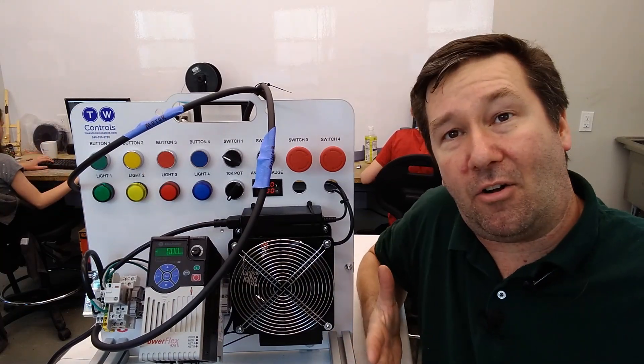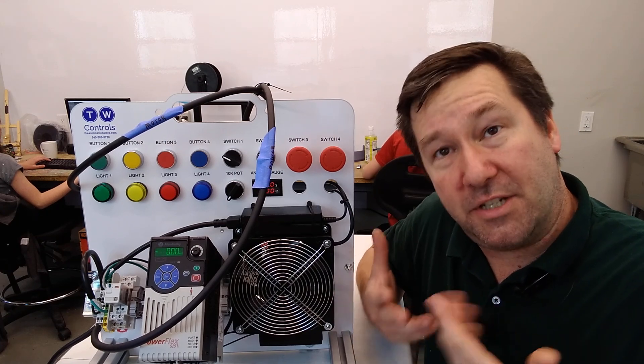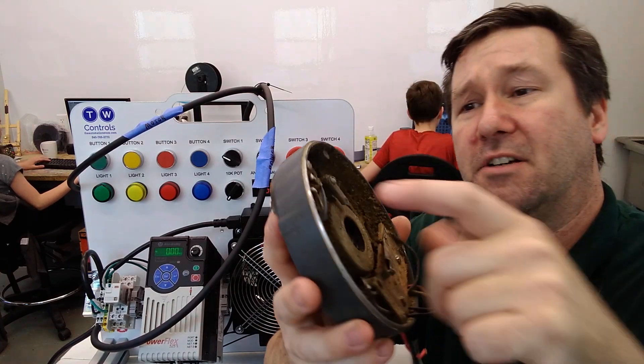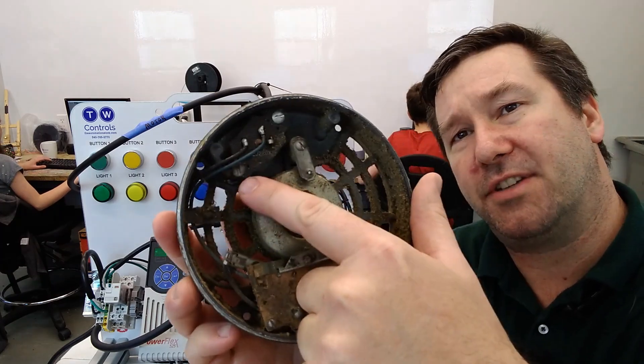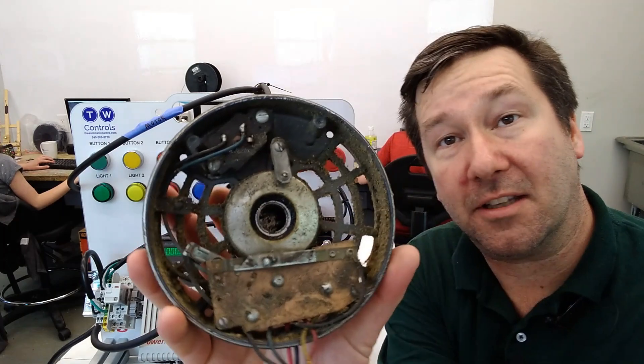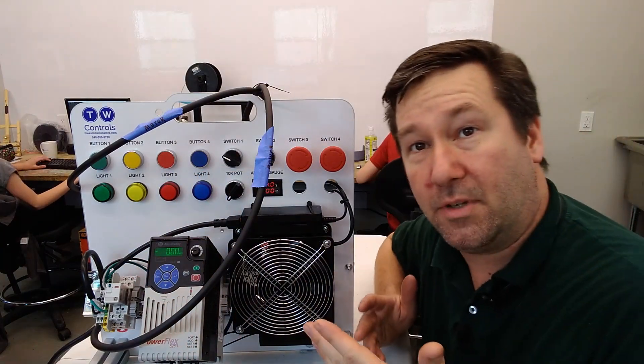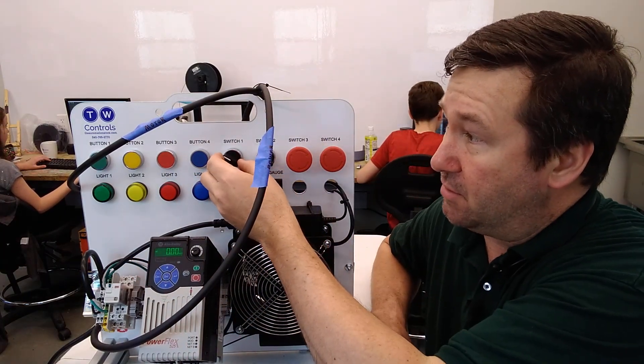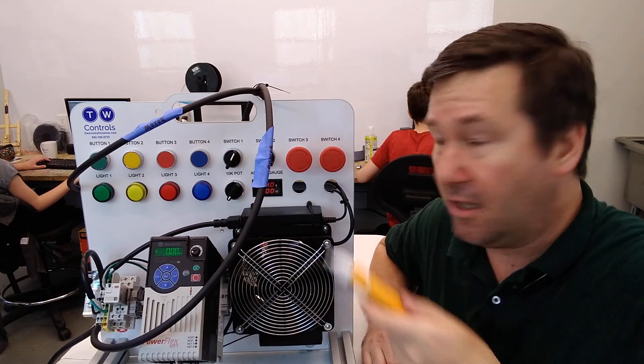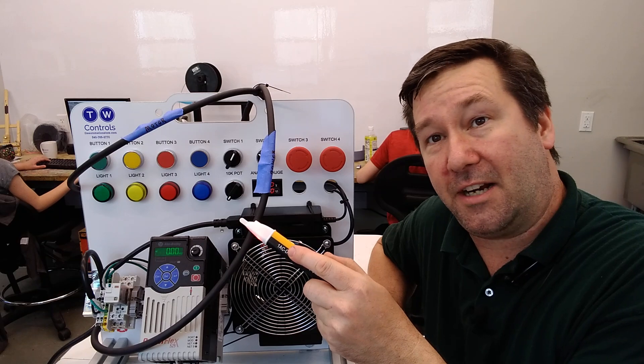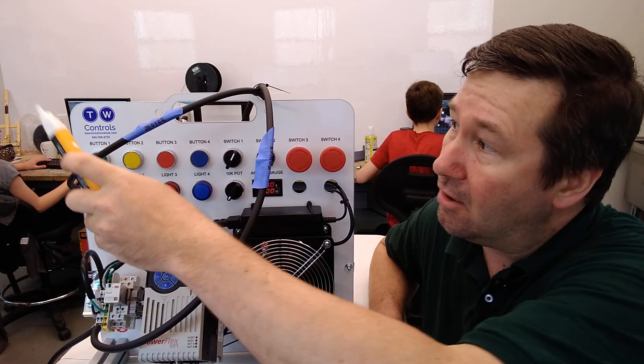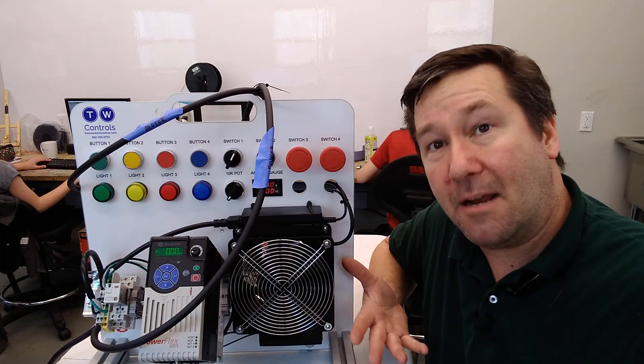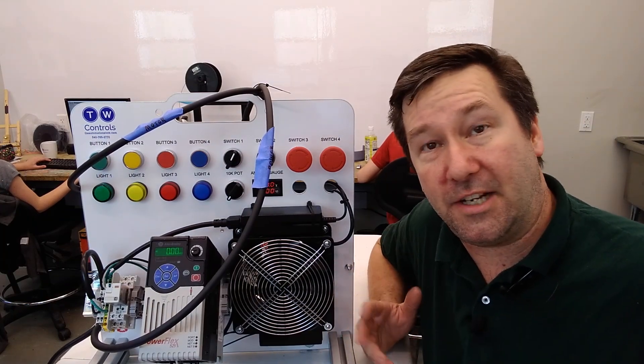So I got a call, and they were asking whether I had a temperature switch for a motor. Now from our single phase motor teardown video, we learned that most of your single phase motors will have a temperature switch in them. And they thought that that was the problem. And they had done a really good job of troubleshooting it because they switched switch one on, and they were getting no motor power. They checked it with their non-contact voltage sensor. They had power going to the saw, and they checked their motor, and they had power going to their motor. But the motor wasn't turning.